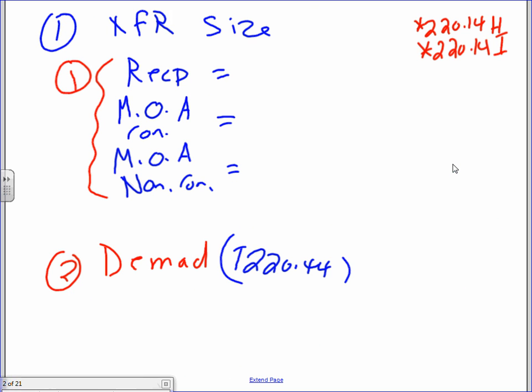The first calculation that you need to do, guys, if you remember 220.14H and 220.14I from the NEC code book, these will tell you what we're going to be writing right now to do the calculation. So I'm going to go directly into the receptacles. The first section is for the receptacle. The second section is for the demand.